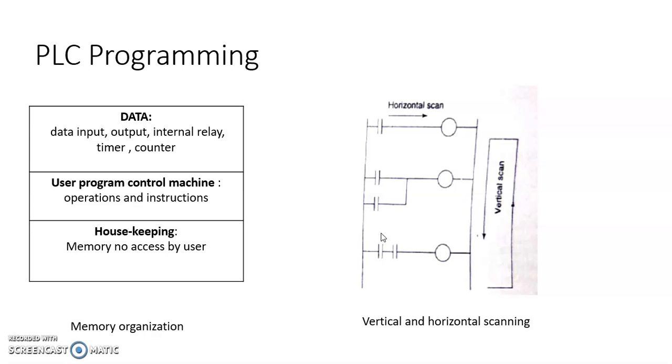Second figure shows program scan. PLC repeatedly takes snapshots of input statement to read values at input and output and energize or de-energize output according to user program. This process is known as program scan. This figure shows PLC scan, which will operate for every few tens of milliseconds. The scan time depends on programming content, length, remote input output scan, etc. Each instruction also requires time for execution.